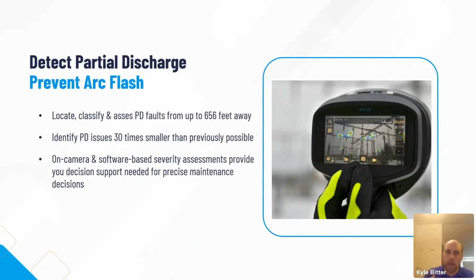You have a great detection distance, up to 656 feet away with the SI2 Pro model, so we can safely scan those areas. If you look at the camera image in the upper right-hand corner next to the normal filter, there's a PD diagram that pops up. This gives real-time feedback if I'm scanning an area and there actually is some type of discharge taking place - that graph will start to populate.